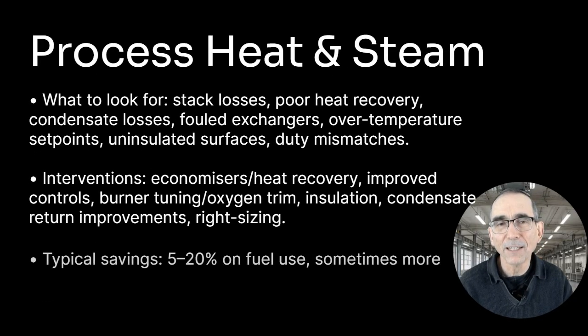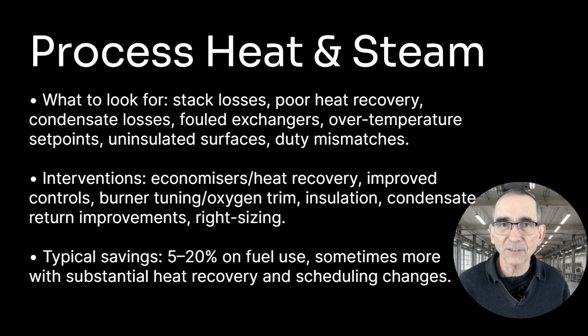Process heat and steam. What to look for? You can look for losses in the flue stack, poor heat recovery, condensate losses. Steam traps are a really common problem. Steam systems tend to inherently become less efficient quickly. Fouled heat exchangers, over temperature set points, using steam for the wrong function when you could just use hot water instead of steam, lack of insulation, duty mismatch. There's a whole lot of stuff to do with process heat and steam.